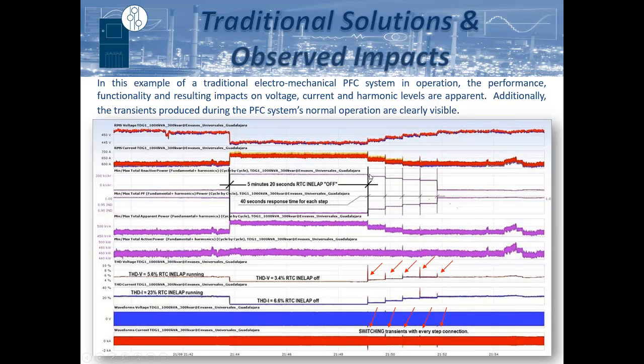And you can see that the functionality of that system will bring in a single group at a time, usually with a total correction time period of well over 2 minutes. So each stage is usually brought in every 20 to 30 seconds. But you can see the impact. There is a rise in voltage from the untreated condition, but oftentimes these fluctuations in between this time period cannot be accounted for just due to how it operates and functions.